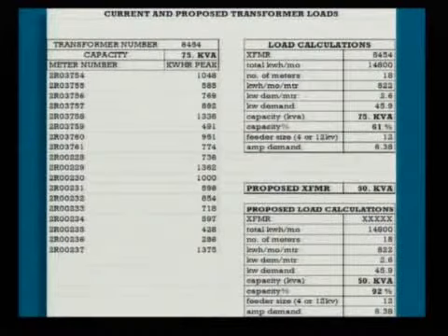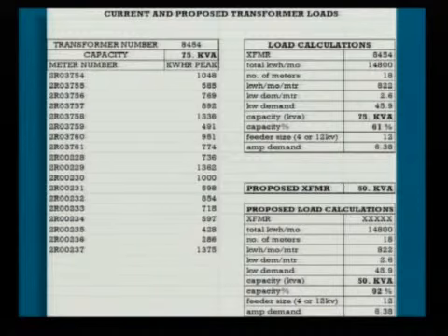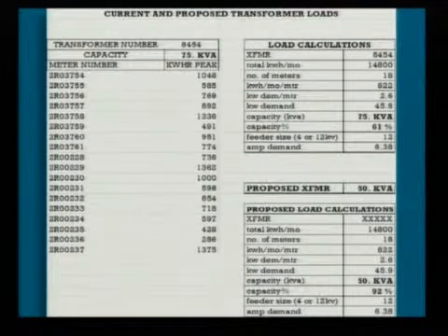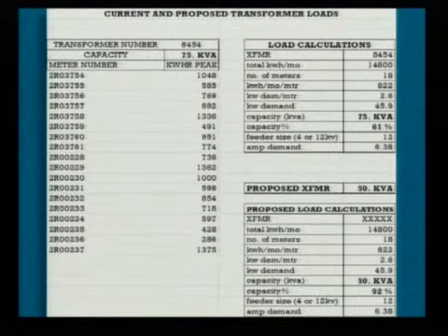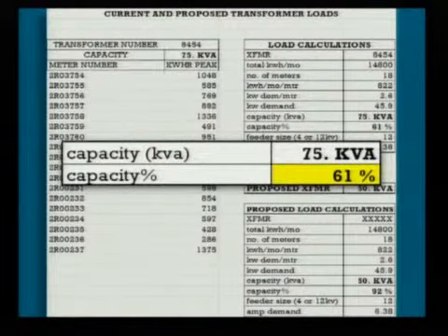So the old way. Now every utility in the nation has some form of this technique, which is how do we figure out how stressed our transformers are. And really the only data points we have to go off of are the monthly reads on our meters. Now, if we know what meters are connected to what transformer, we can input all that data in a spreadsheet, and we get a percentage value. Now, this in no way is exact, but it gets us in the ballpark, and it's really the only way we could estimate. It's our best educated guess of how loaded this transformer was.